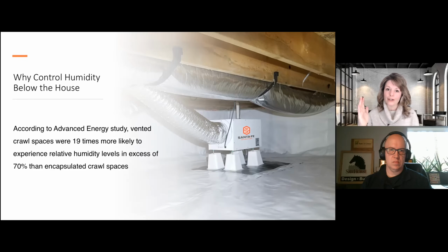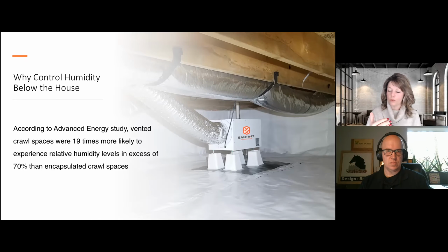And so that supply air strategy basically, the thought is that when the air conditioner is running, it will supply dry air to that crawl space. And again, most of the time the wettest crawl spaces, or the highest relative humidity, is in shoulder seasons. So there's probably not a lot of AC runtime going on. Our crawl spaces are cool automatically, just like our basements. So you're taking dry, cold air and putting it into a crawl space, which if it's 65 degrees in the crawl, the RH is automatically going to increase. For every degree that the temperature drops, the RH goes up 2%. So automatically RH is going to go up.